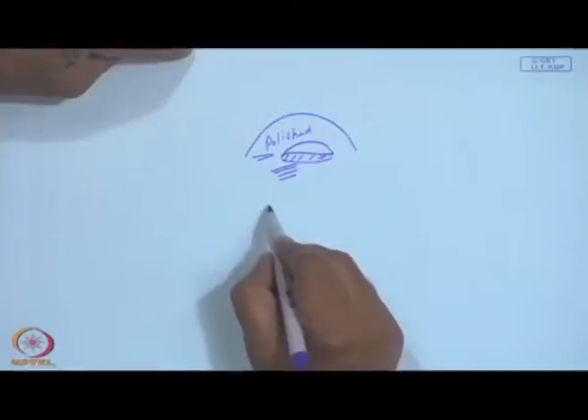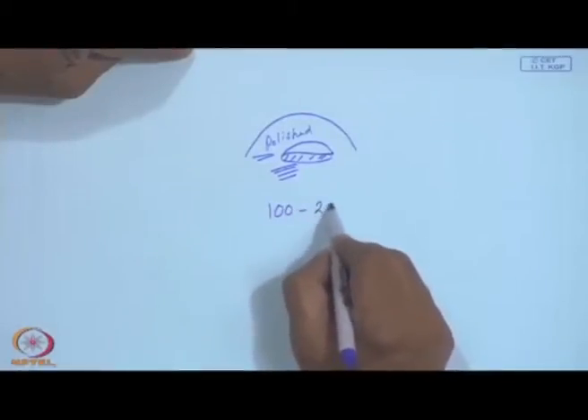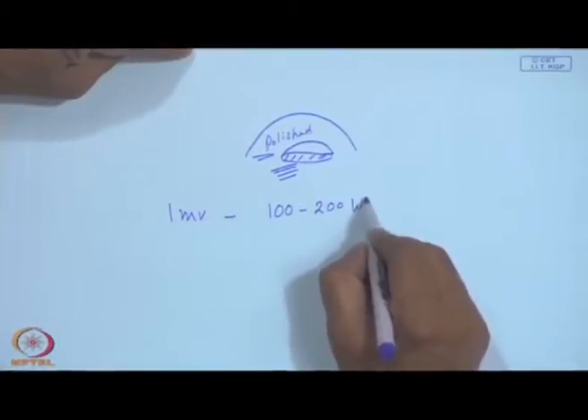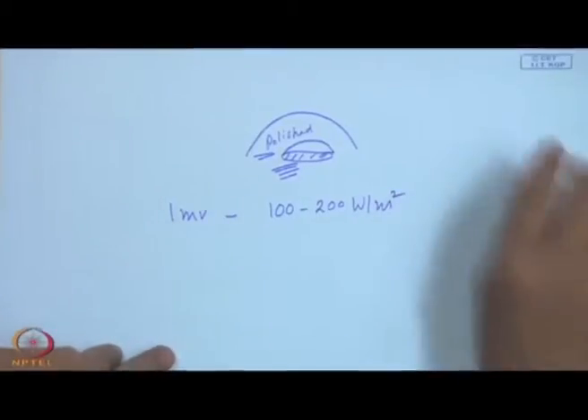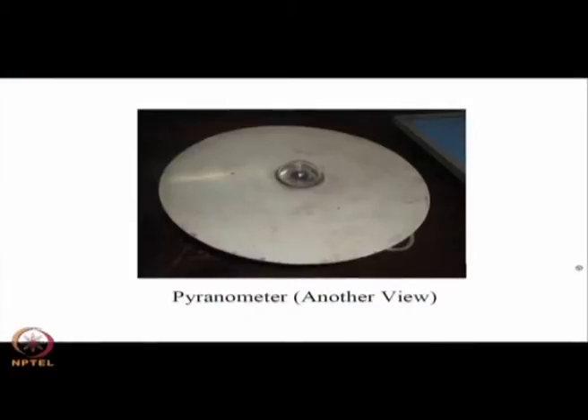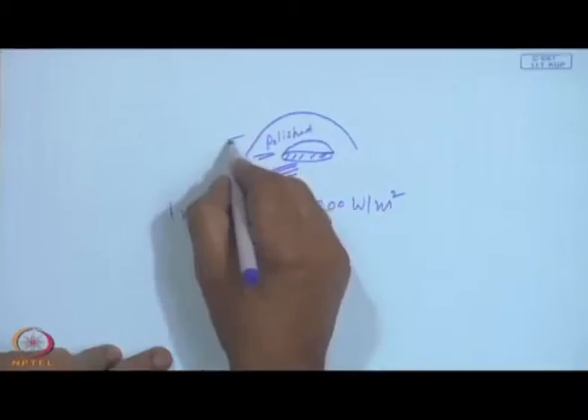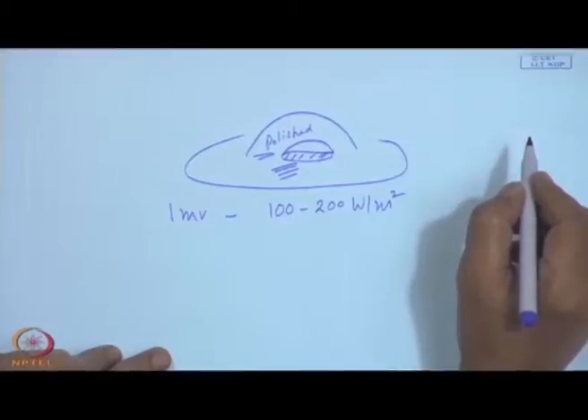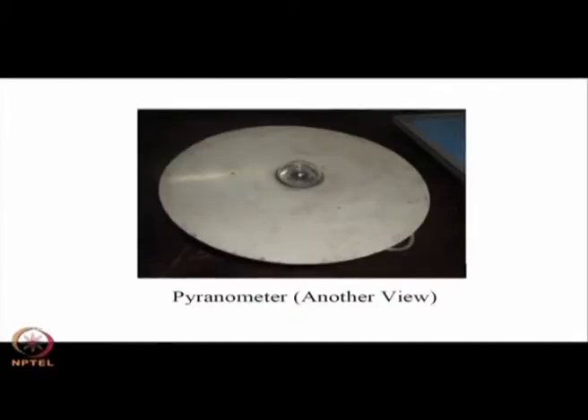Typically the output is around 1 millivolt for about 100 to 200 watts per square meter. This is another view, and you must be wondering why I have not mentioned the surrounding disc. This surrounding disc ensures that no other radiation is reflected onto the sensor, so that it measures only the total radiation, or global radiation, falling onto the sensor.